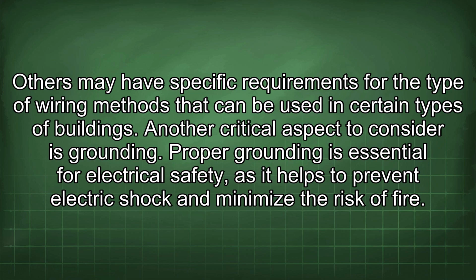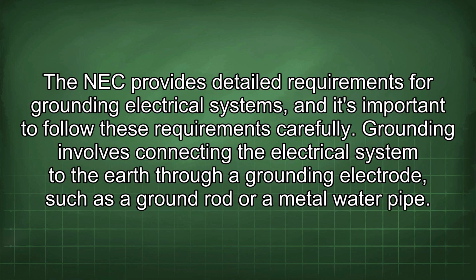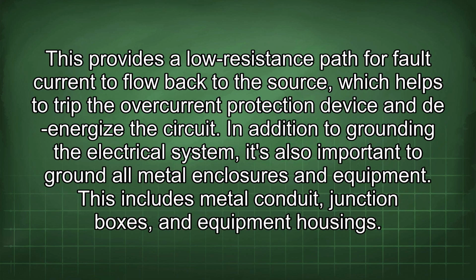Another critical aspect to consider is grounding. Proper grounding is essential for electrical safety, as it helps to prevent electric shock and minimize the risk of fire. The NEC provides detailed requirements for grounding electrical systems, and it's important to follow these requirements carefully. Grounding involves connecting the electrical system to the earth through a grounding electrode, such as a ground rod or a metal water pipe. This provides a low resistance path for fault current to flow back to the source, which helps to trip the overcurrent protection device and de-energize the circuit.